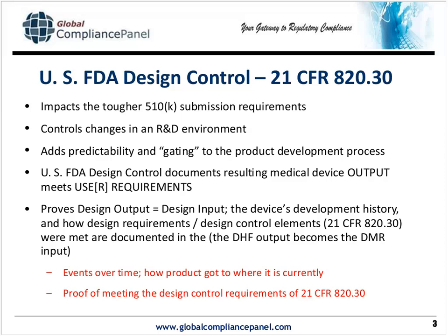Your design control paperwork, documentation, if you will, has to show that your design input has in fact been met by the design output. And this is done by various verification steps that, again, we'll discuss and illustrate throughout this discussion. Now, the design history file output becomes the device master record input. So that's kind of a key deliverable of the design history file and the design control process.